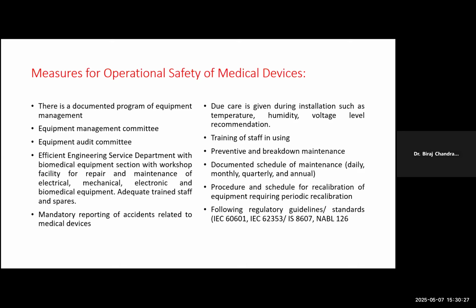Then preventive and breakdown maintenance. There should be a calendar for when to do the preventive maintenance, and you should maintain a register for breakdowns. Record the time and date when the breakdown happened, the time and date when you informed the vendor or your workshop, when they came, and whether they have redressed it or it is still pending. So we must maintain the breakdown register. Then document the schedule of maintenance, daily, monthly, quarterly, or annual, as per the recommendation of the manufacturer.